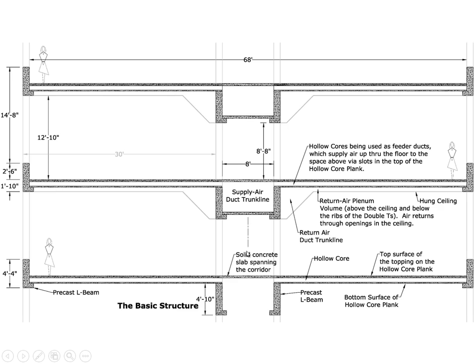In the next diagram, we keep the same basic structure but add a hung ceiling with an interesting shape. It comes off at the level of the bottom of the L beam for a smooth ceiling transition. This plenum volume can accept air and conduct it back to a volume that becomes the return air trunk line — return air flowing east and west. So we have a return air volume or plenum above the ceiling, below the ribs of the hollow core planks. Air returns through openings in the ceiling. In this scheme, we're talking about using the hollow cores as feeder ducts to supply air, going up through the floor to the space above via slots in the top of the hollow core plank.